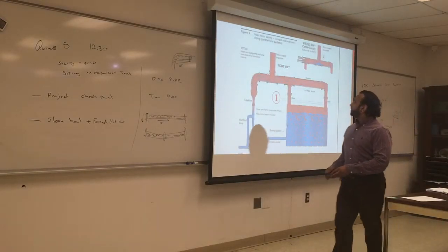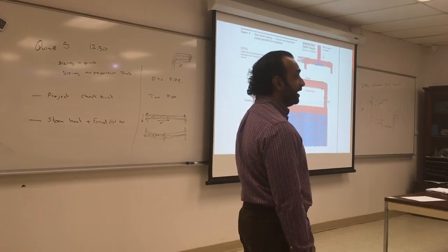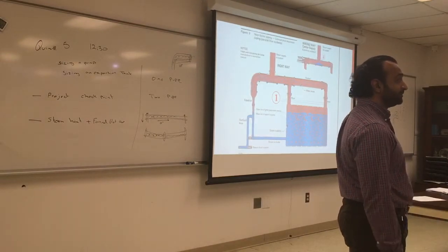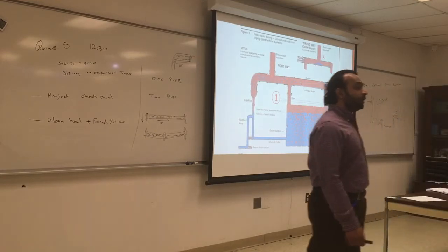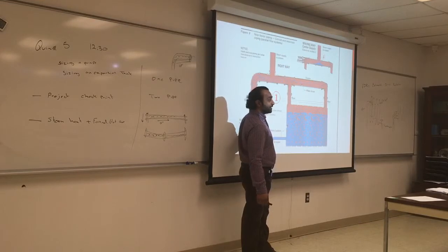Near the boiler piping, there's something called a Hartford loop, which is very important, and it's the code now to have in any boiler, especially for steam. The reason it was called the Hartford loop is it was invented in Hartford, Connecticut. What's in Hartford, Connecticut? A whole bunch of insurance companies. Yes, and they were tired and sick of paying for failed boilers. So a lawyer realized that all those boilers were failing because of low water. And he thought of this idea to keep the water level in the boiler at the same level as the water in the condensate line.